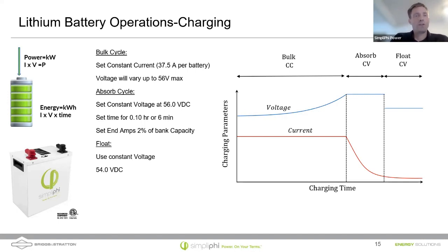You do this at a constant current. We normally set our batteries up under standard temperature conditions to charge at 37.5 amps, which is the C/2 rate for a 48-volt battery - so 37.5 amps per battery. If I have 2 batteries, that would double to 75.